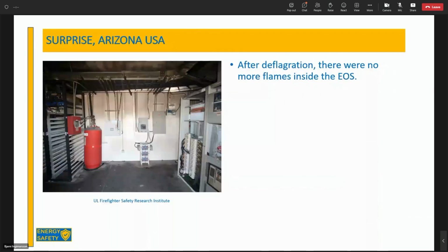After the deflagration, there were no more flames inside the energy storage system. So what you see here, there's not a lot of damage. This is a gas explosion, nothing more. This is a gas explosion by accumulated explosive gases coming from the battery.